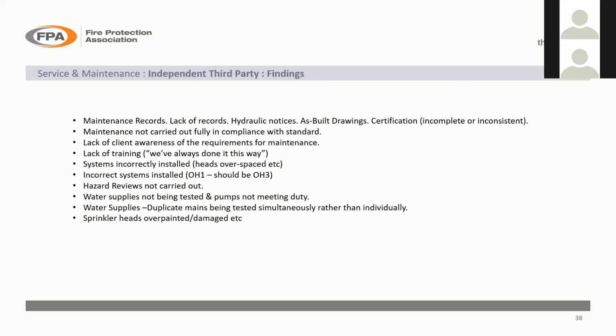Sprinkler heads being overpainted and damaged, particularly with concealed heads. This is where you look up to the ceiling and you can see there's a sprinkler head, but it's just a flat plate that you can see. Once these have been overpainted, there's a good chance that they won't operate. First of all, they won't detect the fire quite as quickly because you've got a layer of paint covering it. Secondly, by the time it does come to operate, the layer of paint might actually just be holding the cover plate on, which means the head might operate above the ceiling, and if it doesn't drop down below the ceiling, obviously you're going to lose coverage in that area.